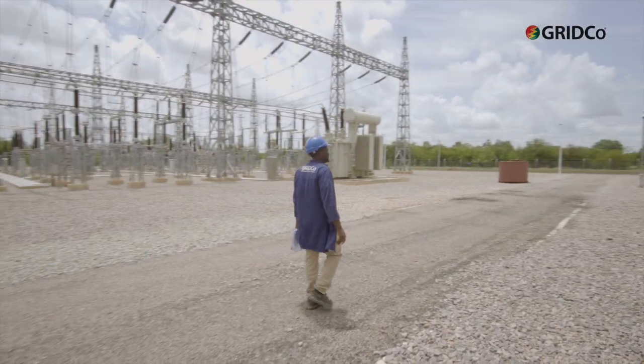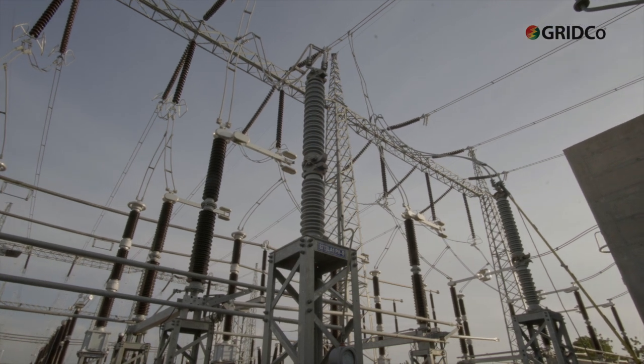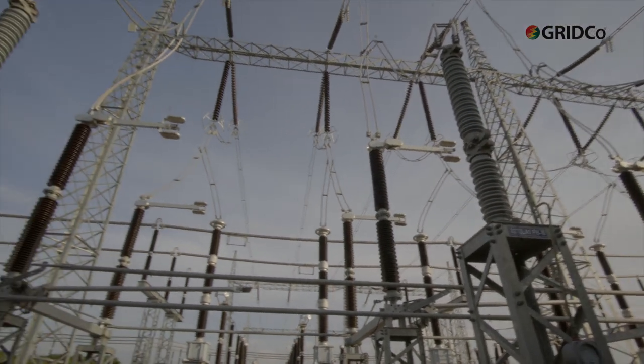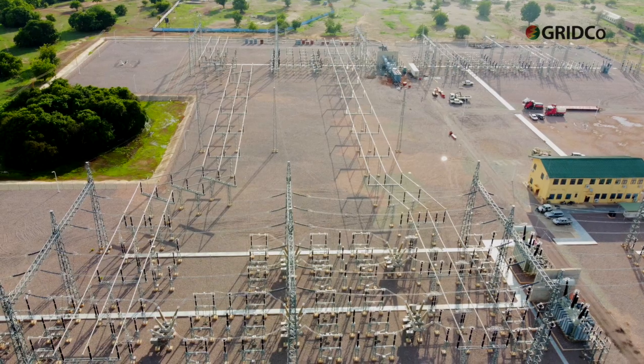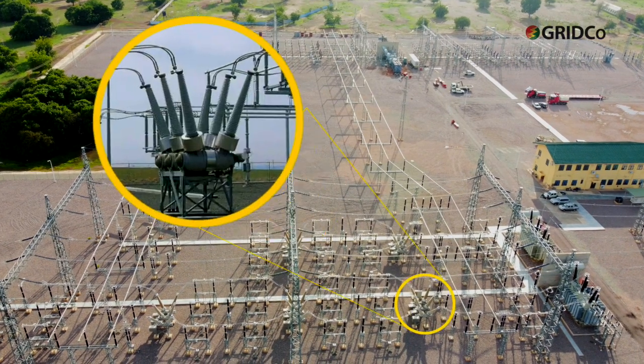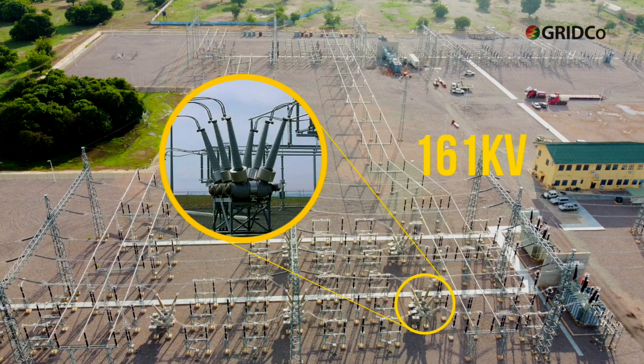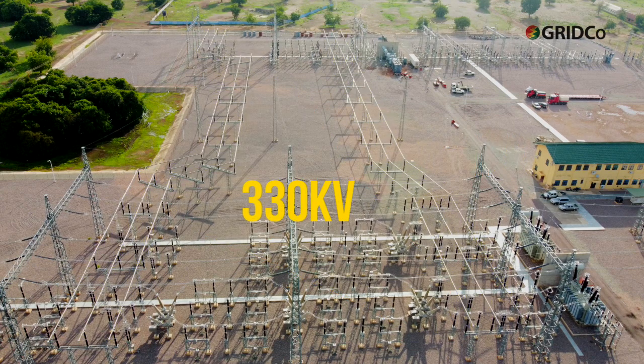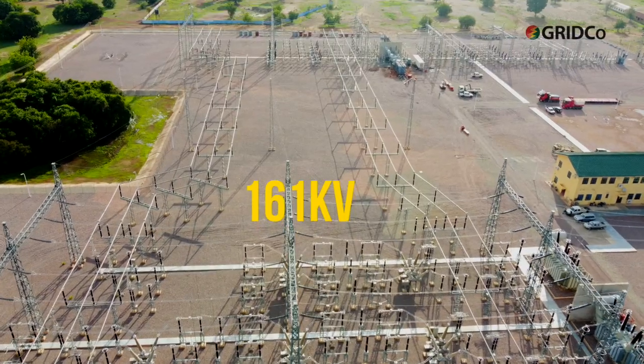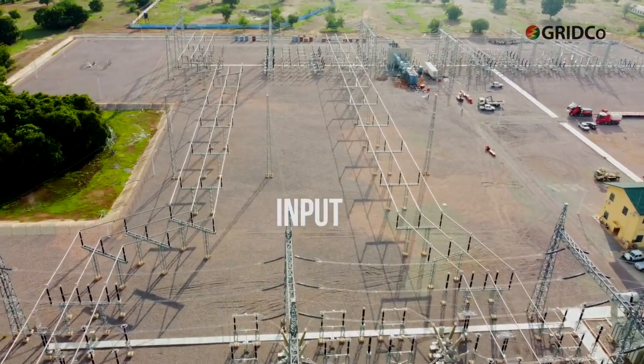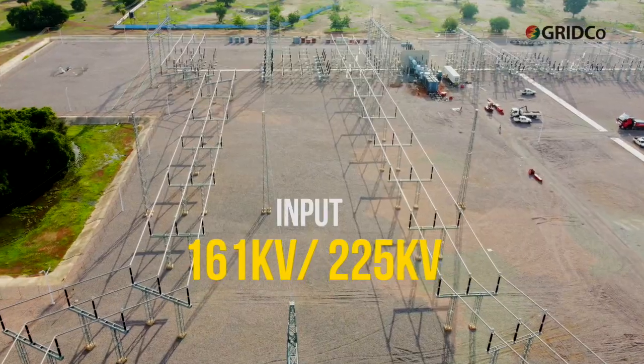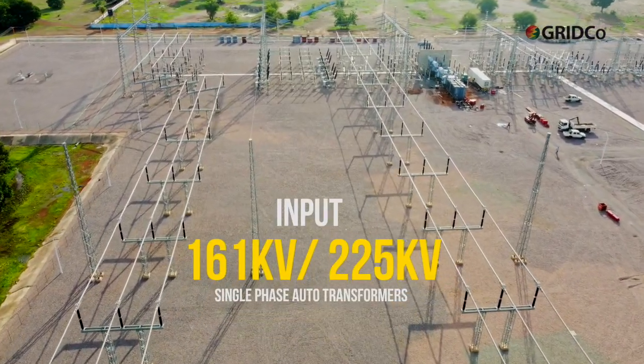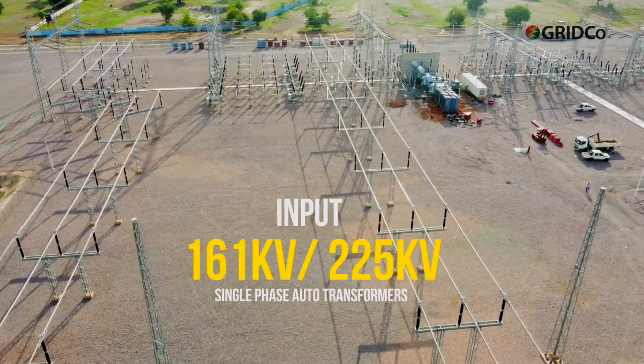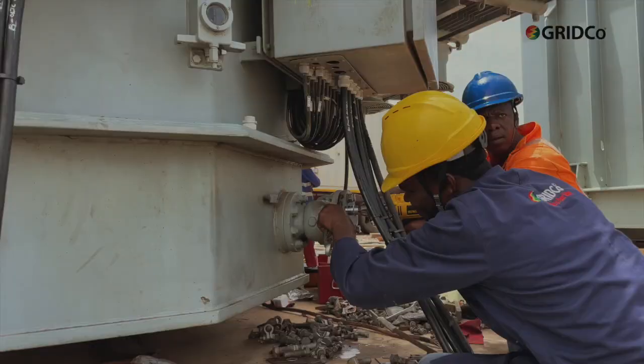To assist us with the conversion, a jumper is used as a bypass to link the 161 kV bus bar voltage to the 330 kV bus bar voltage. The 330 kV circuit breakers of the sino-hydro transformer will now be energized at 161 kV voltage after the bypass. The circuit breaker is closed and the bus bar's 330 kV becomes 161 kV. The converted bus bar now becomes the input of the new 161 kV / 225 kV single-phase auto transformers. This is to provide hot standby supply of electricity to Sonabel in Burkina Faso.